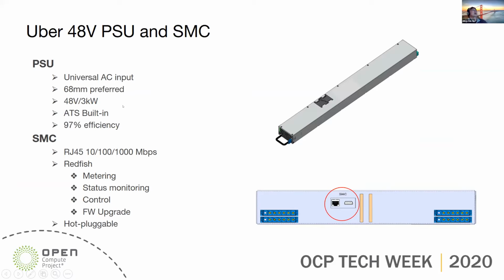Since we have a dual AC input, but we still want to save some efficiency and not use N plus N redundancy, we implement an auto transfer switch into the power supply design. So for efficiency, we ask for 97% peak efficiency.